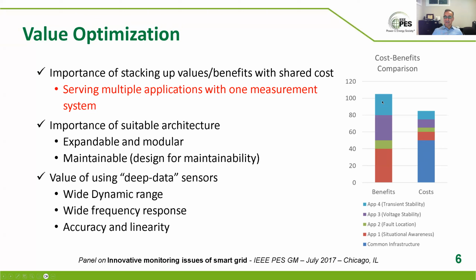But each of them gives benefit. In this case, if you had only one application deployed, the overall cost would be higher than the overall benefit, so it's not wise to do it. But if you actually install all four applications, not just situational awareness, but also fault location, voltage stability, transient stability, these are just examples that you could do with PMUs to some extent, if you put all of those, then the values stack up.